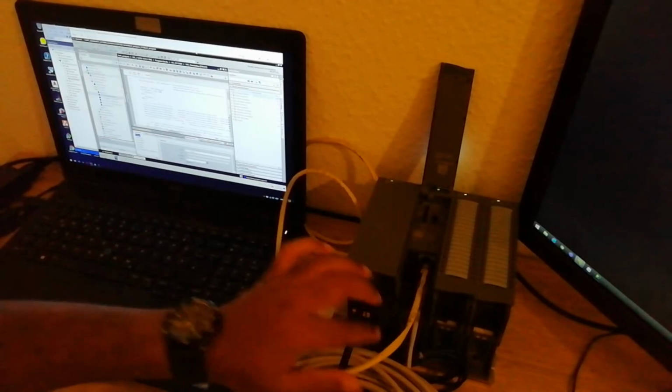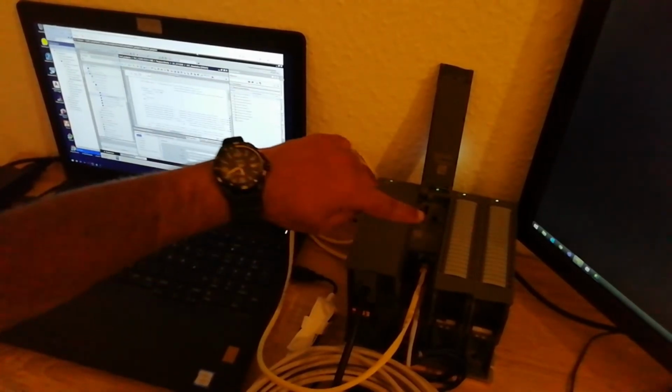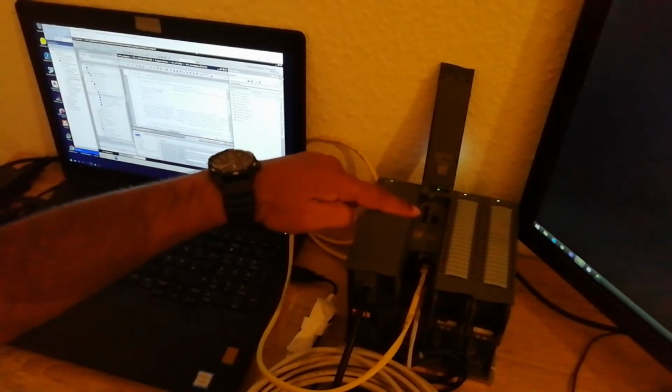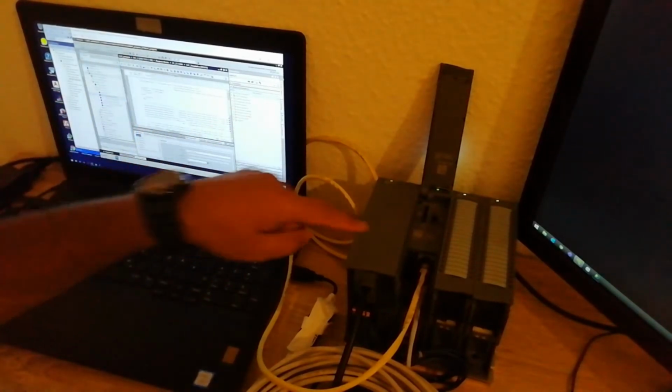Okay, so two different things, because we have the possibility with two Profinet ports in the S7-1500 PLC. I didn't need to use a switch, but in case of maybe S7-1200 or smaller PLCs, you need to have a switch, because then you don't have two Ethernet ports to connect the same PLC to two different instances running in the same machine. All right.